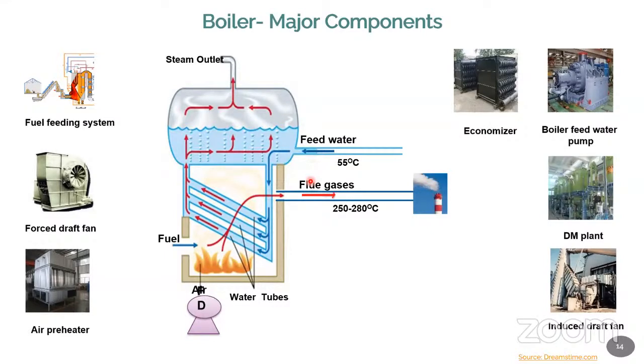So two things you have to remember. Number one, the forced draft fan should pump air in sufficient quantity. When it is higher, problem. When it is lower, again problem. Okay, now this is for the first case. Second case, now you produce the steam, no problem. You produce the steam and you let out the steam to the process. Now the process requires steam, let us assume at 8 bar pressure or 7 bar pressure or 6 bar pressure. Now the steam is going to the process. The steam boiler is at some pressure and the steam will be at some pressure.